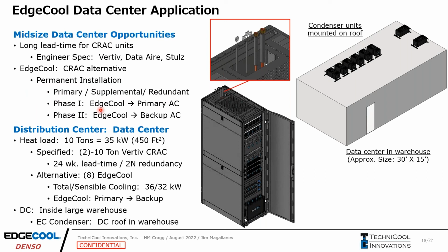Phase 1, we could be the EdgeCool, could be primary air conditioning, and phase 2 could be used as backup because of the long lead time. So what we've seen is working with FedEx, they have a distribution center. They have a 10-ton heat load in their data center, 35 kilowatts, and a 450 square foot data center. They specified 2 10-ton Vertiv units, but the lead time was 6 months, and they're also looking for 2N redundancy. So what they were looking at is using EdgeCool as an alternative.